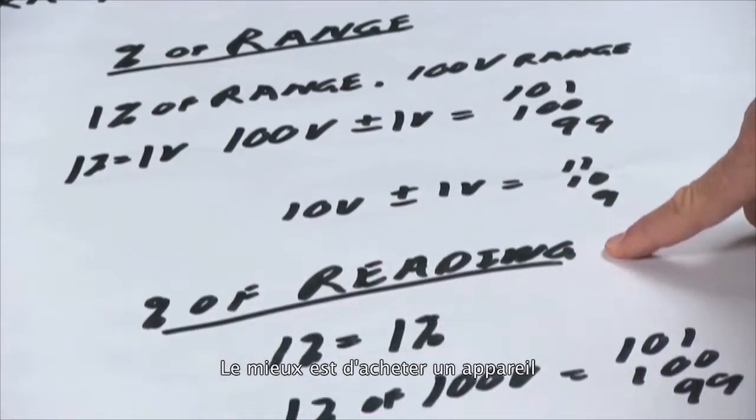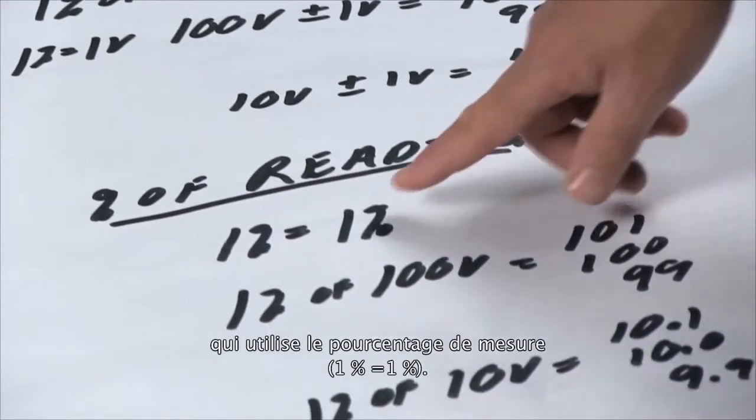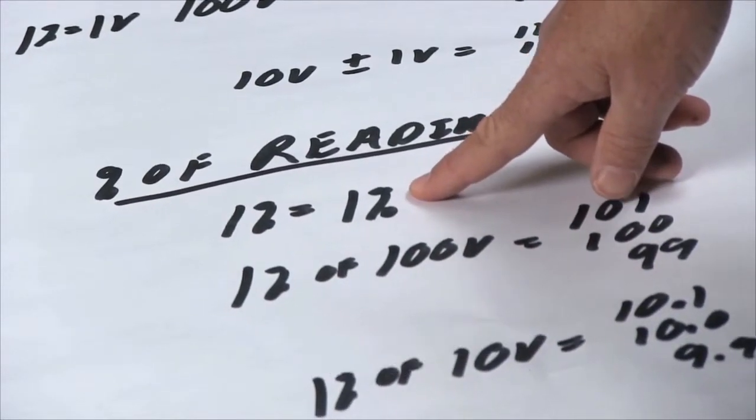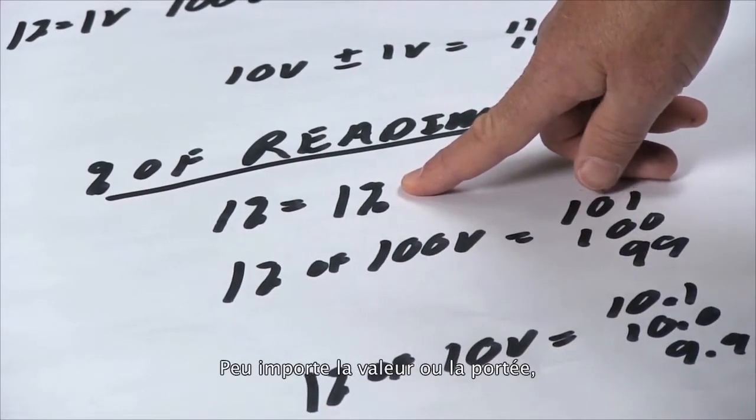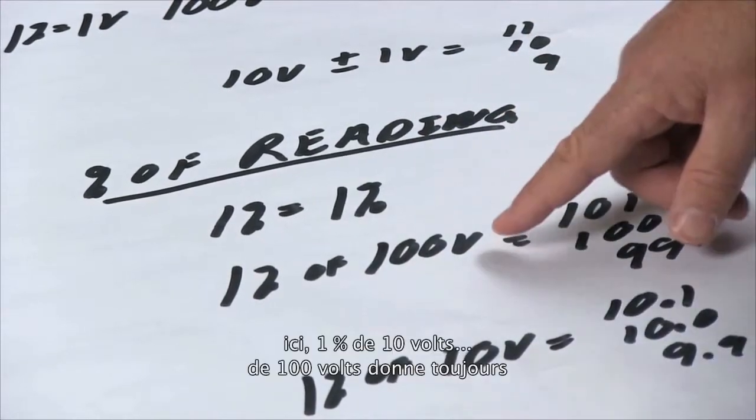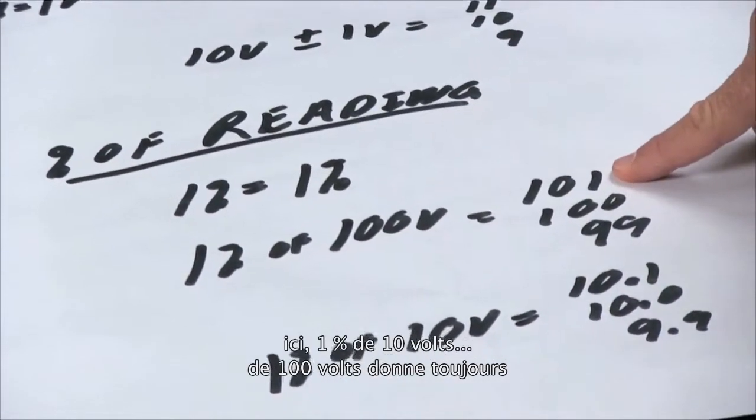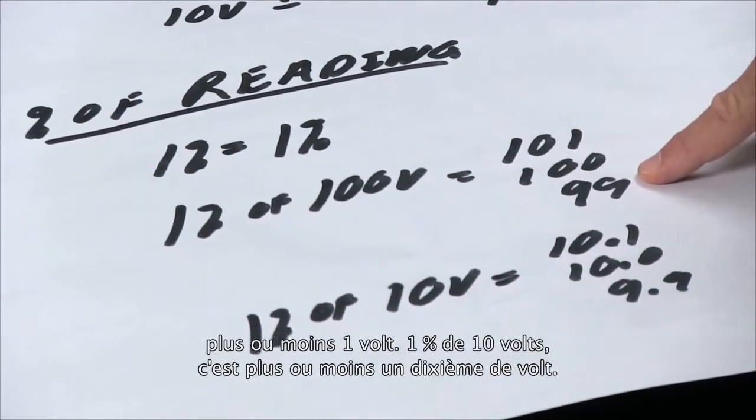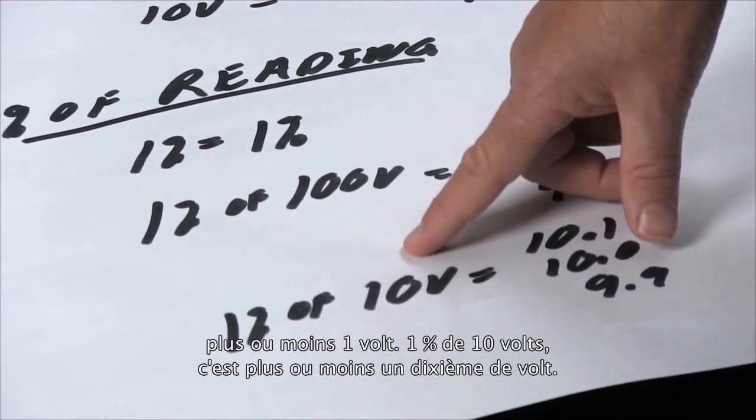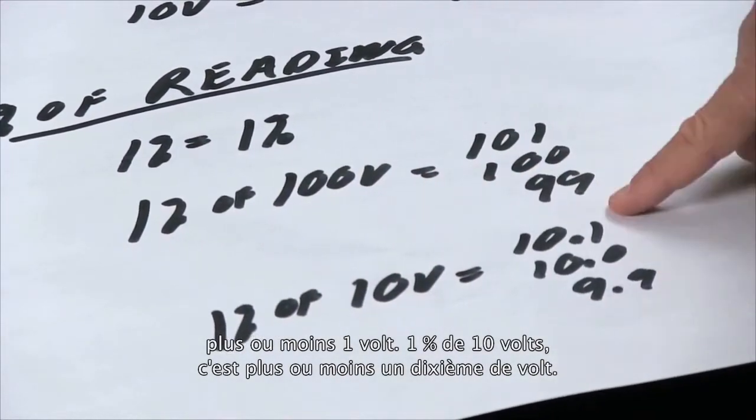A better way is to buy an instrument that has percent of reading, and then one percent is one percent. It doesn't matter what value or what range you're on. So here, one percent of a hundred volts is still that plus or minus one volt. One percent of ten volts is plus or minus a tenth of a volt.